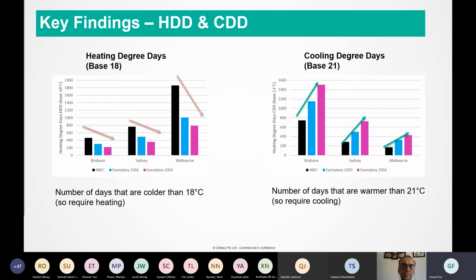Then we summarize them into heating degree days and cooling degree days. And the whole reason for that is because as the number of heating degree days increases, then heating energy increases, therefore our boilers, our heat pumps, our electric duct heaters. And with cooling degree days, as the number of CDD increases, of course, our cooling energy increases.